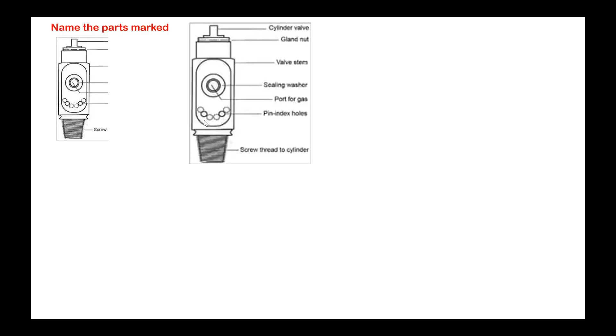Name the parts marked here. Again, the same thing we have seen earlier. This is the cylinder valve stem. Then there is a nut. Here also a leak can happen. Right? So that will be the gland nut. Then there is the port for gas. Then there is the Bodok seal. These are all the holes for the pin index. And this screw only will be threaded into the neck of the cylinder. Okay? So this is the whole thing.